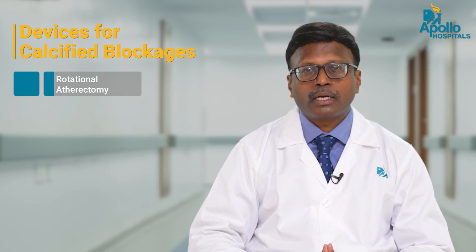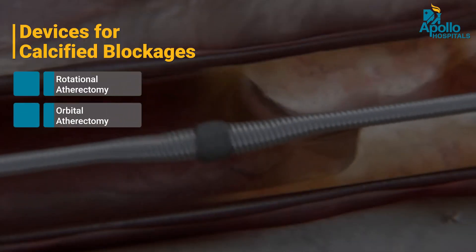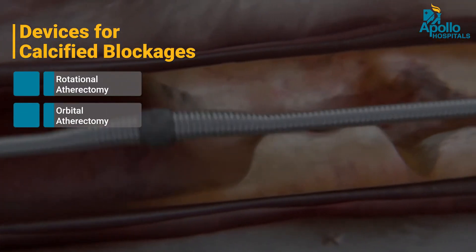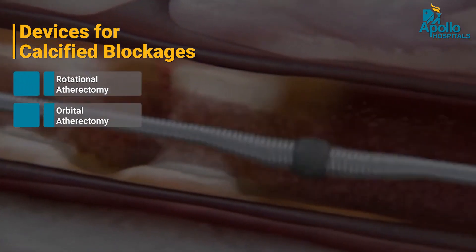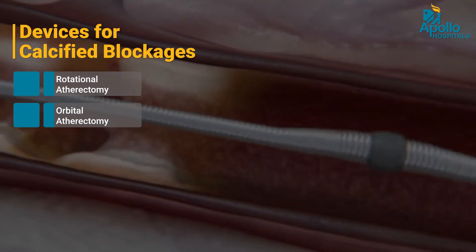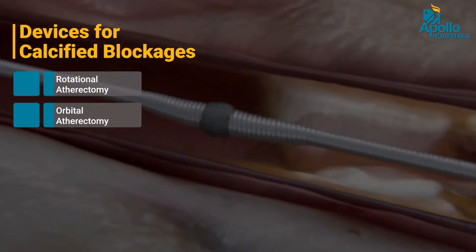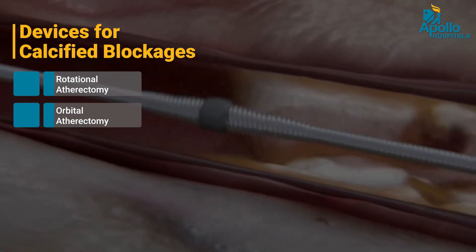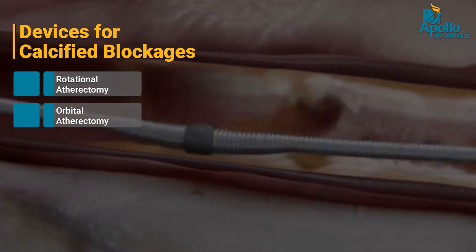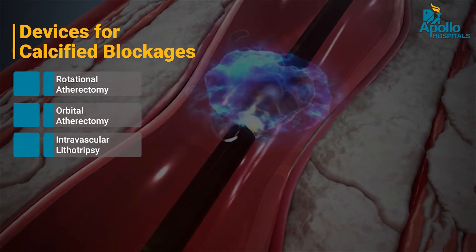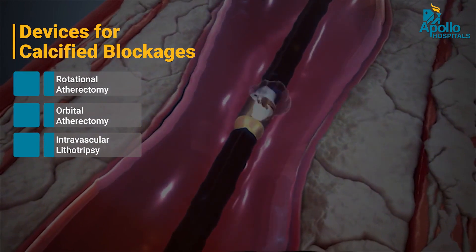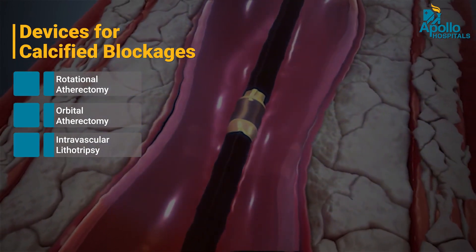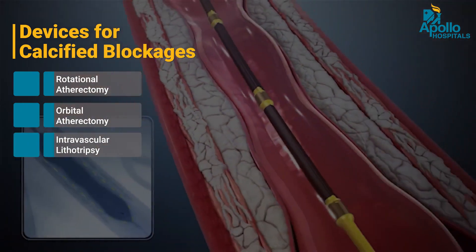Another device introduced in the last year is orbital atherectomy — an orbiting device. Just like the earth rotates on its axis and also around the sun, it has two rotations, going inside the blood vessel at 80,000 RPM. It cuts even deep calcium into small pieces. A third device is intravascular lithotripsy, which emits shock waves to break the calcium. These are the three important devices used nowadays for calcified blockages.